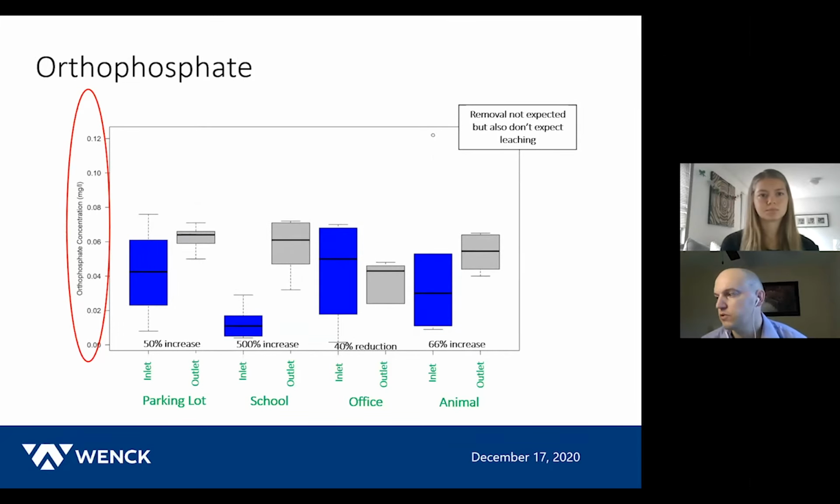Orthophosphate, similar story as to total dissolved. Perhaps if you're just looking at percentages, concerning, but the concentrations are not. It's concerning that there could be increases moving through the filters, but we need to do more to understand exactly when our samples were taken and dive into the data a little bit more. I'll get into that here in a few slides.